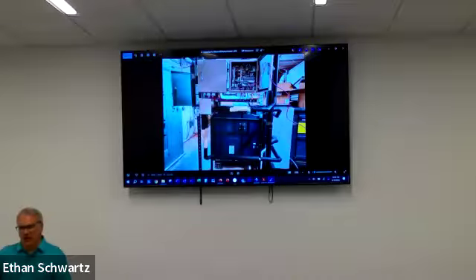There are still going to be separate operating circuits, each responding differently. And with Fujitsu, you cannot have two indoor units and two wired remote controllers cross over on two separate refrigeration circuits. You can have two indoor units that have one wired remote on the same refrigeration circuit, but it can't cross over the two because the units can't control that operation. Does that make sense? And they work very well.